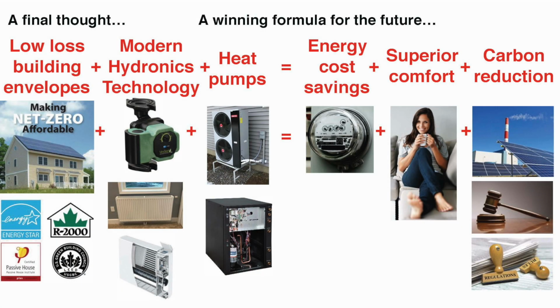And finally, carbon reduction. So this is a formula that brings together all the trends that are happening in the market, and it allows us to take hydronics into this market and be in a very good position. We need to get that message to builders, to politicians, okay, and also to energy office people. I've been working with a lot of different state energy offices. They have really no idea. If I say distribution efficiency, no idea. They are very hung up on things like AFUE, SEER, COP. That's their word. They just assume that we can drop a heat pump into whatever and it's going to work, and that's not the case. We have to make our distribution systems compatible with those heat pumps.